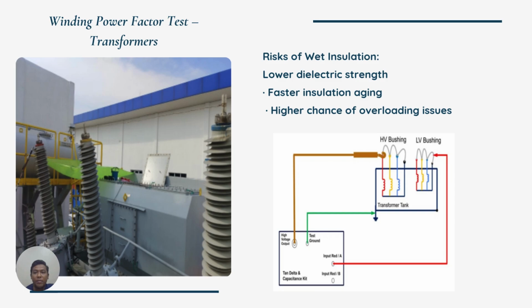When moisture is present, especially with heat, it forms acid inside the transformer. That acid weakens the insulation and causes it to fail more quickly, reducing the life of the transformer. This brings serious risk. The transformer may become overloaded and the insulation loses its dielectric strength, meaning it can't handle voltage as well. All of this leads to faster aging and a higher chance of failure.